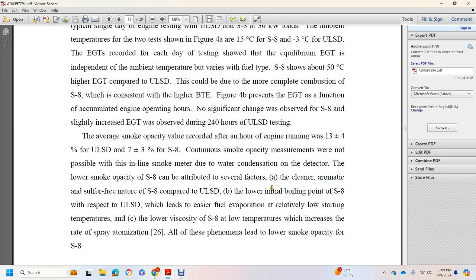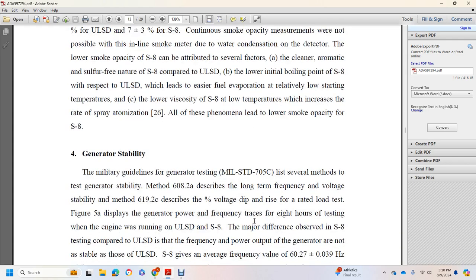The low smoke opacity with the S8 is attributed to several factors: A, the cleaner, aromatic- and sulfur-free nature of the S8 compared to the ultra-low sulfur diesel; B, the lower initial boiling point of the S8 with respect to the ultra-low sulfur diesel, which leads to easier fuel evaporation at low starting temperatures; and C, the lower viscosity of the S8 at lower temperatures, which increases the rate of spray atomization. All of these phenomena lead to lower smoke opacity in S8.